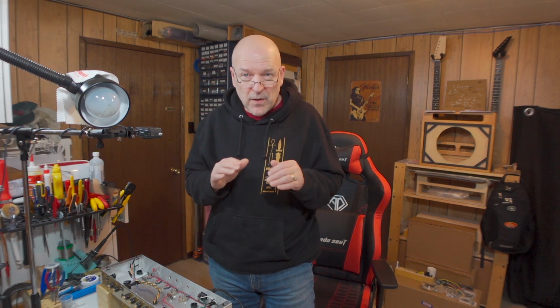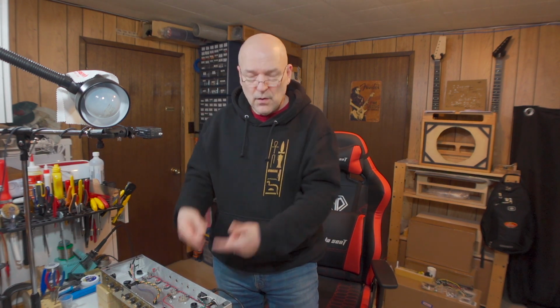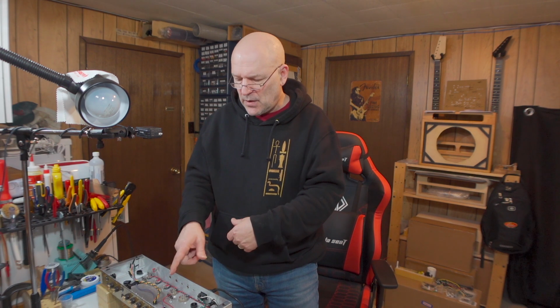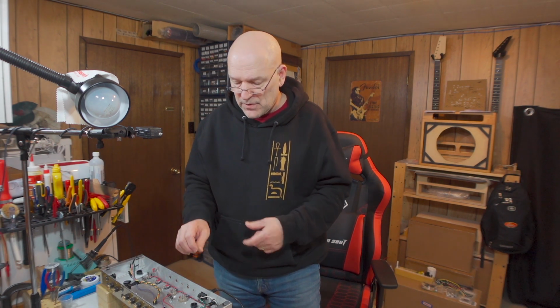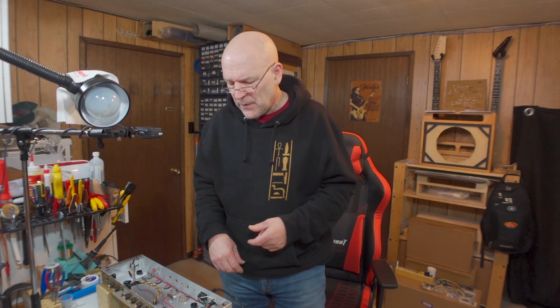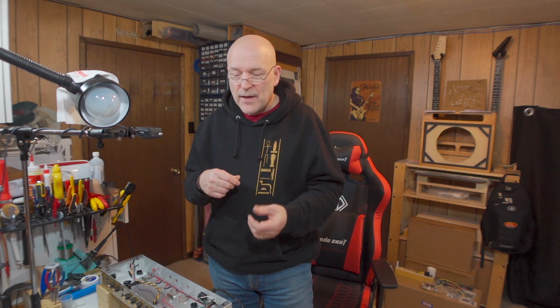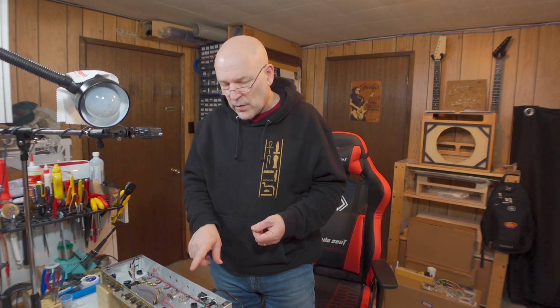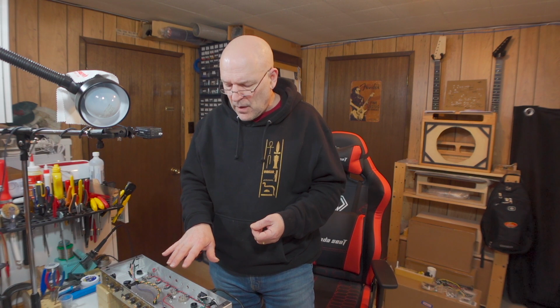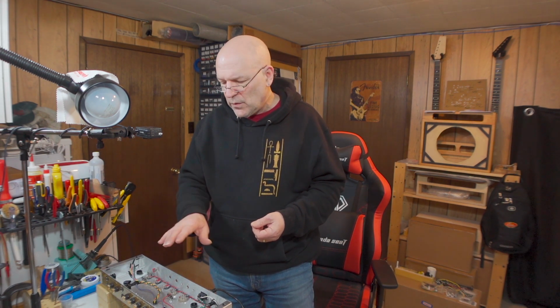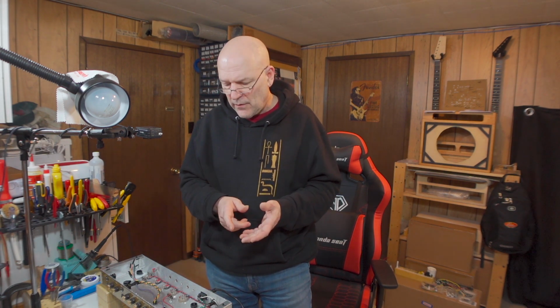So we're going to do a sniff test, and we're going to do a noise test. It's normal for a transformer to hum very quietly. If you get down there and you notice a little hum or buzz, that's normal. It's if it's noticeably loud, if you could hear it right here, that would be a problem. Same thing with the arcing. If I could hear arcing right now, that would be a problem. Sometimes you won't hear the arcing till you get a little bit closer. So we will do that smell test and that hearing test. And we aren't going to touch anything in there because the amp is live, but when we are done testing, we will disconnect the power, and then we are also going to do a field test and visual inspection of the transformer to make sure everything's okay.